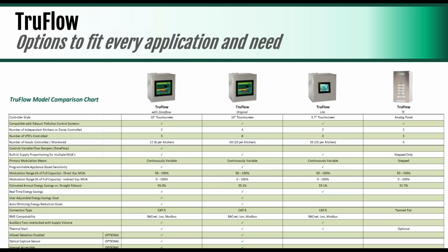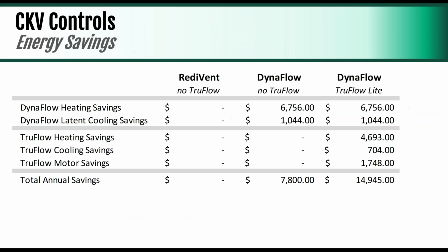This is just basically an overview of different TruFlow models. We've actually consolidated these, and I should update this. But we've really got two versions now: a TruFlow with zone flow damper, so that's allowing you to put really as many hoods as you want on one exhaust fan, or a version without the zone flow dampers, and that's what we call TC. And they all have touch screens now, and can all modulate pretty significantly to provide energy savings.